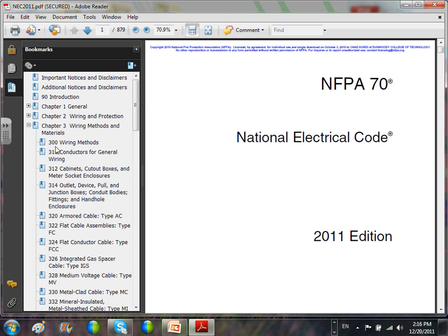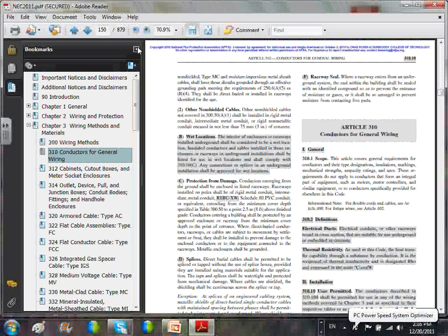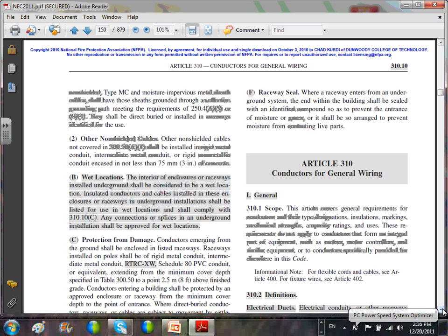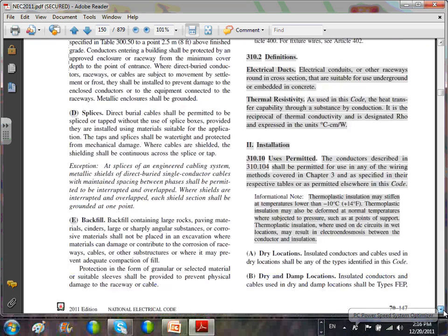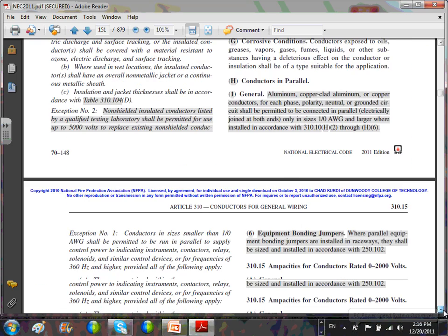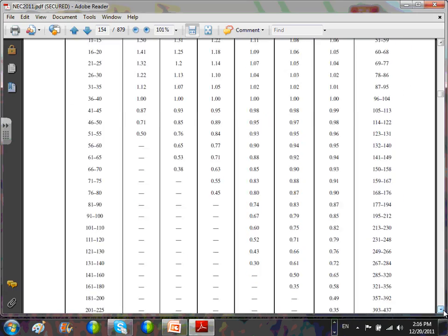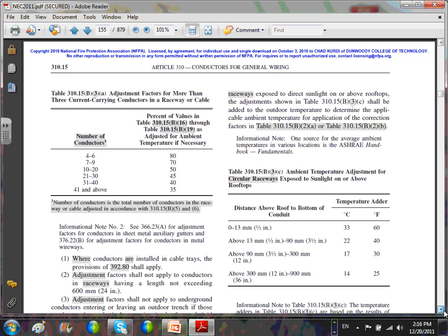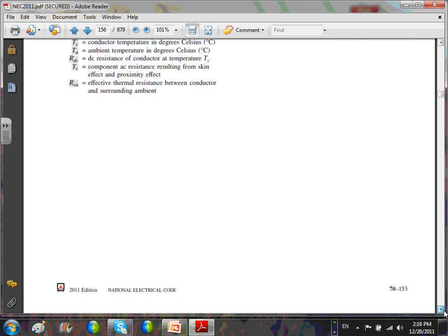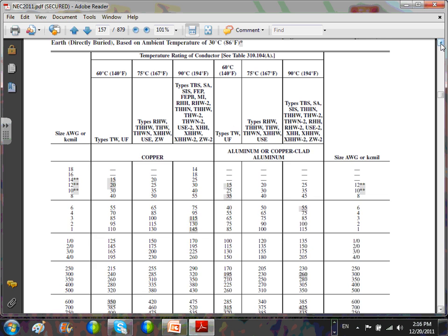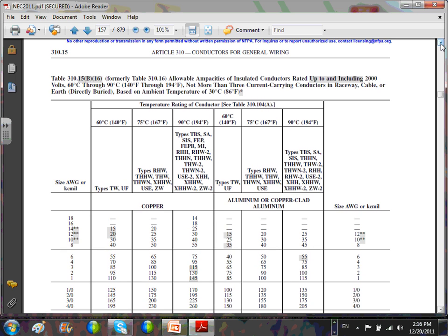Do you guys have your codes with you? No? Okay, you don't have to. So this is where most of the sizing happens. If there's one table you should know and never forget, it's this table here. This is what we call Table 310.15(B)(16). You size all the conductors for any type of motors, any type of equipment, based on this table.